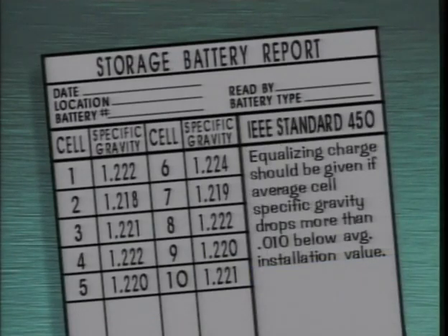IEEE Standard 450 also states that an equalizing charge should be given if the average specific gravity of all cells drops more than .010 from the average installation value.